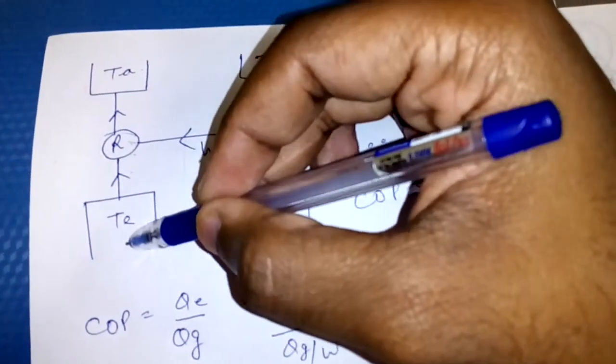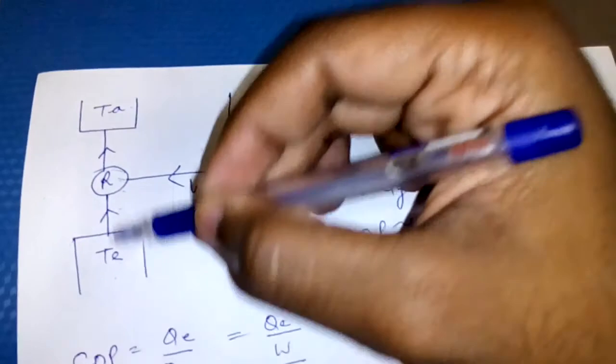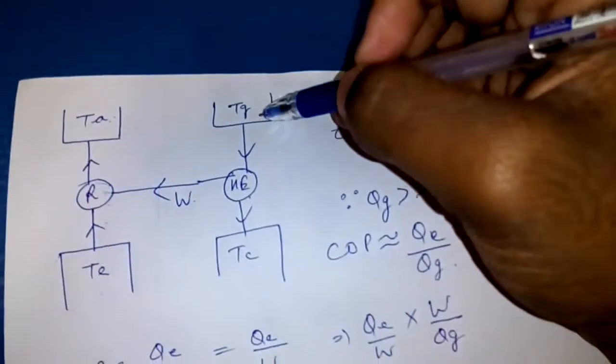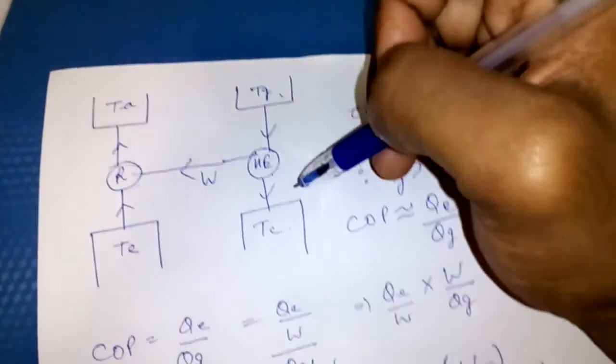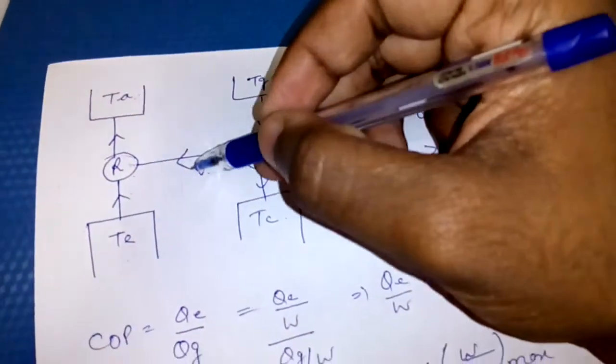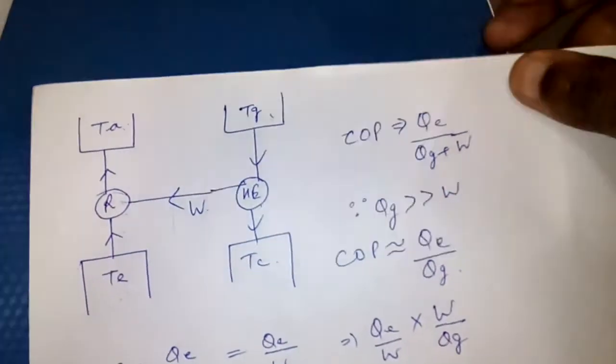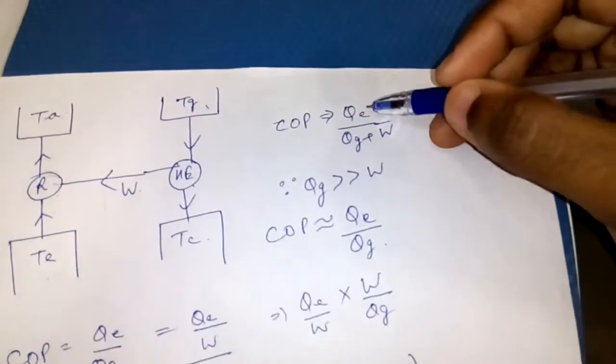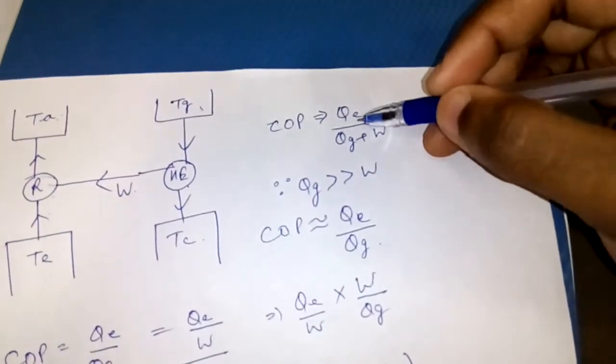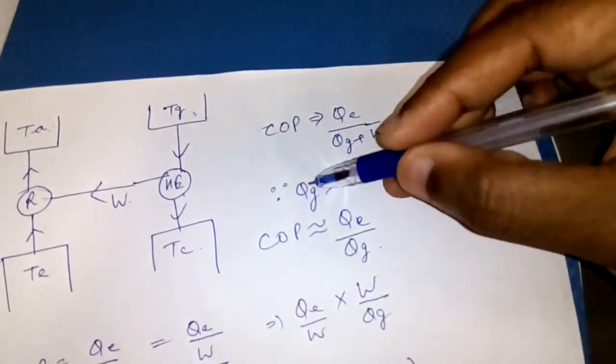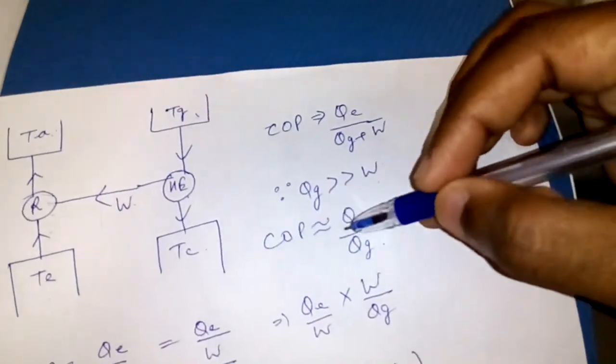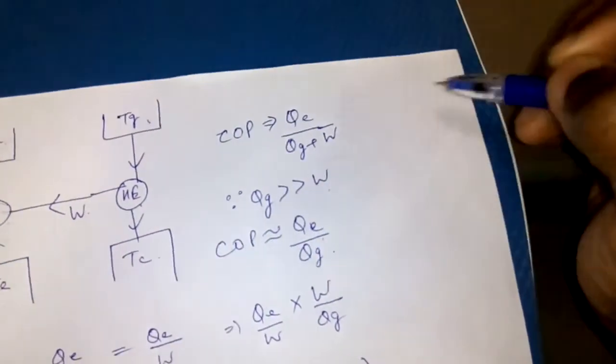This is TE corresponding to the temperature of evaporator, TA corresponding to the temperature of absorber, TG and TC corresponding to the temperature of generator and condenser respectively. This is the W, the pump work. Now since our COP was QE upon QG plus W, whereas QG is much larger than W, we can write COP nearly equal to QE upon QG.